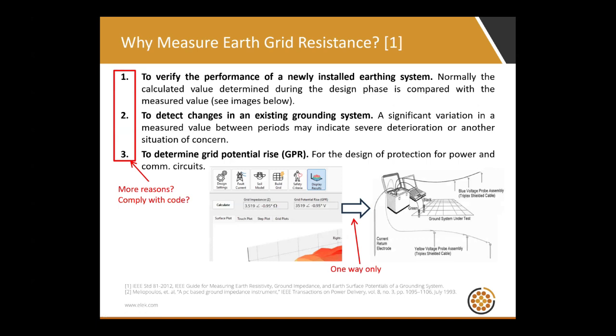Why do we measure grid impedance? These are the main points taken from IEEE standard 81, just to remind us: to verify the performance of a newly installed earthing system, to detect changes in an existing system, so we can perform this test immediately after the construction of a new system or on an existing system. We can also use the test to determine the grid potential rise, which is another safety consideration.